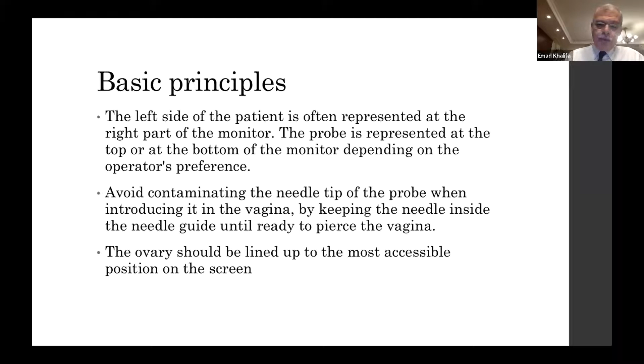Avoid contaminating the needle tip or the probe when introducing it into the vagina. You introduce the probe in the vagina. Don't try to introduce the needle tip after introducing the probe deep in the vagina. You have to keep the needle inside the needle guide until you reach the uppermost part of the vagina. The ovaries should be lined up to the most accessible position on the screen.